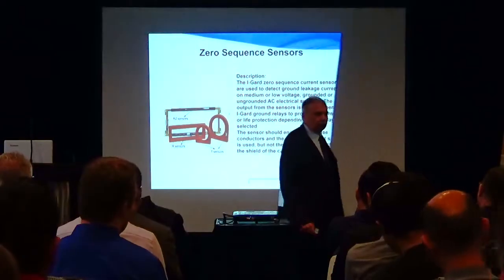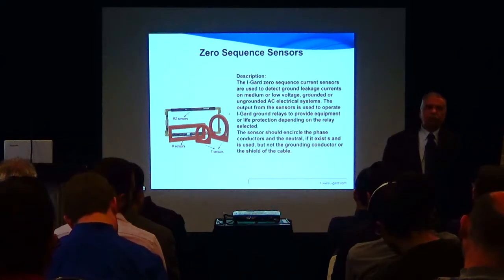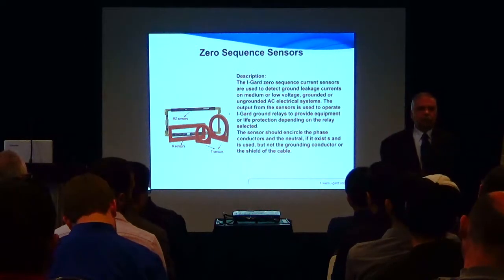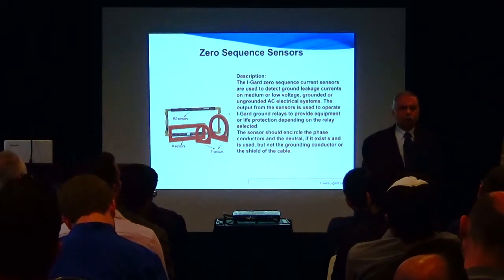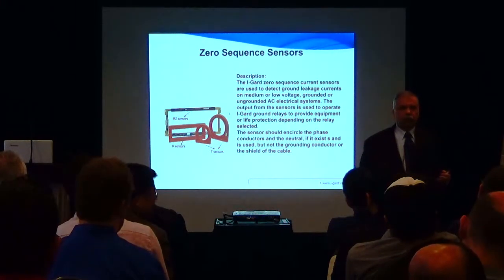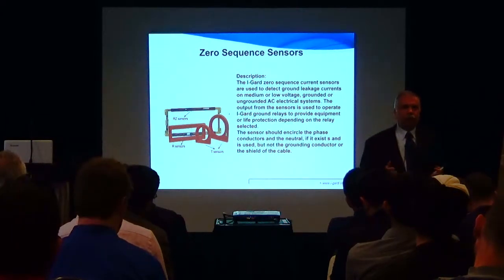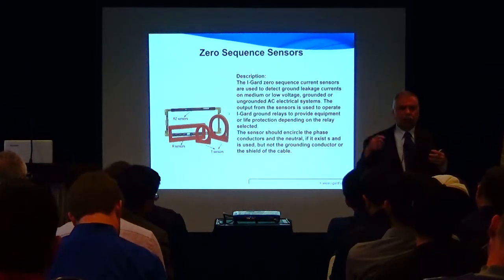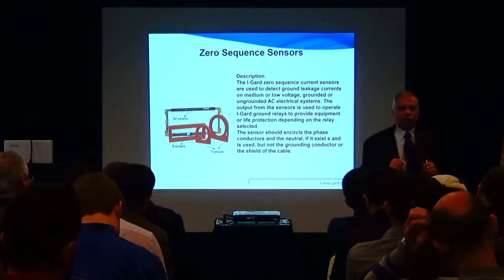These are all low voltage. So if you are going to apply them at more than 5 kV, 15 kV or whatever, you need a bushing on the cable to provide the 95 kV insulation. This is low voltage insulation. The supplier of the switchgear does the testing. Okay. So he has a 15 kV bushing, that's appropriate for 95 kV BIL or higher. For 150 or 200 kV BIL, the sensor is a low voltage sensor on the outside of the bushing with a large window.